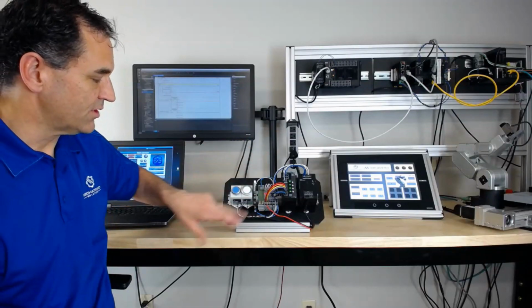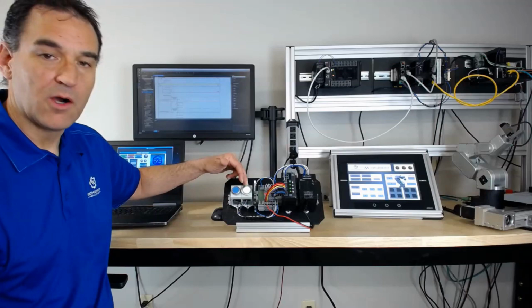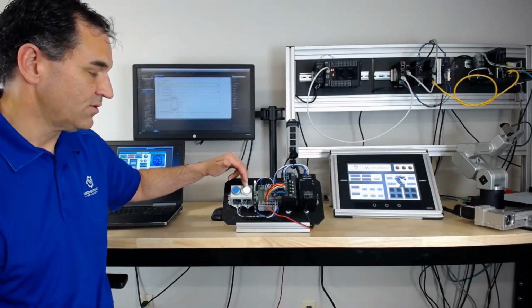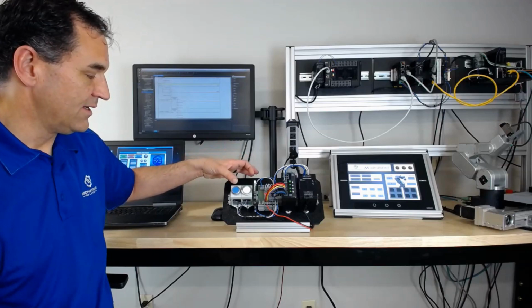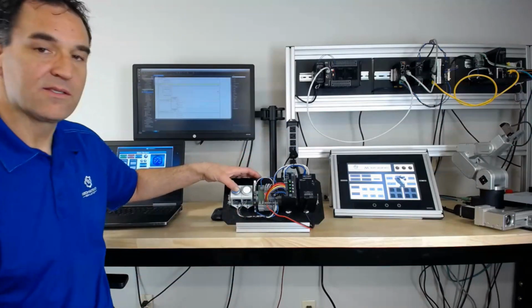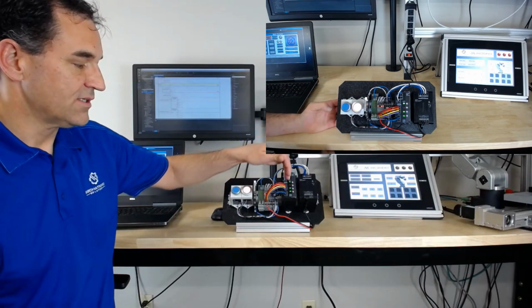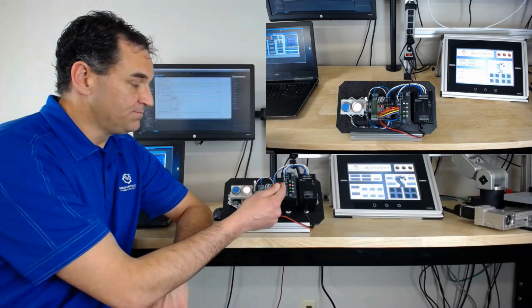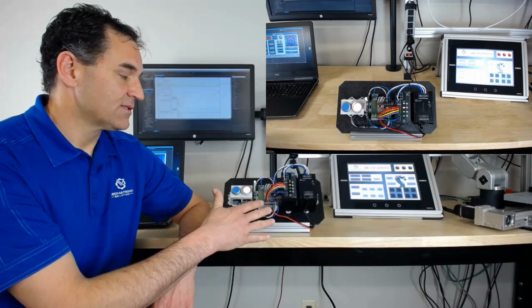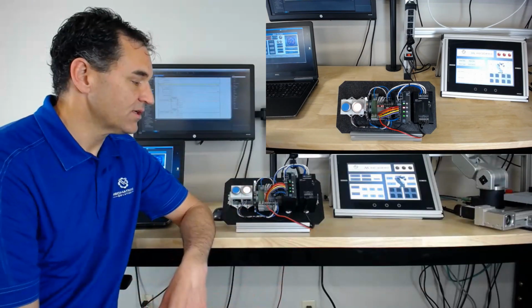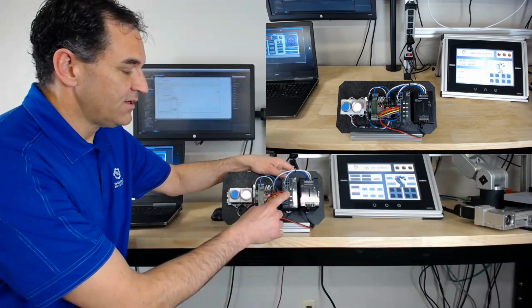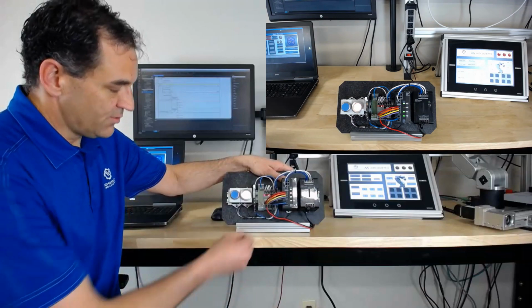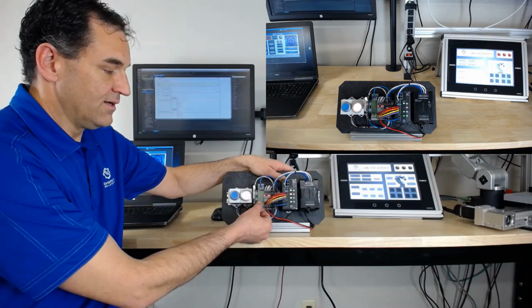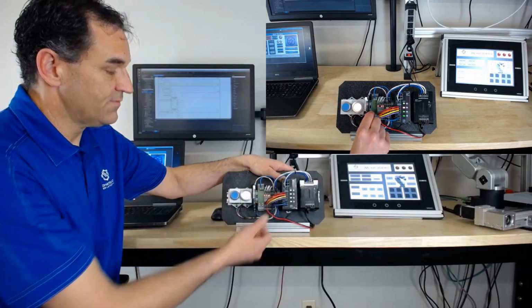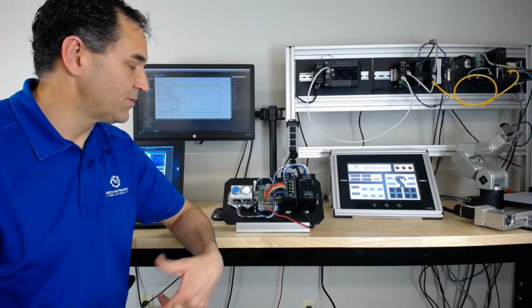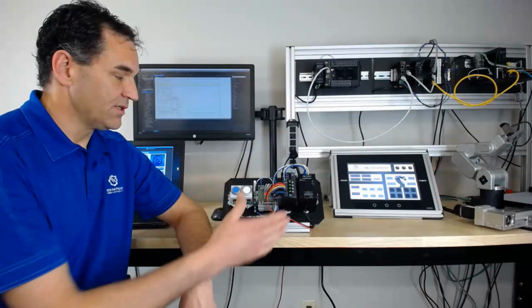I have a load tied to circuit 2, and I've got the alarm output tied to this indicator light. So you'll see this go red if we have a trip. And then I've got a remote reset. So I'm going to put a load on circuit 2. You'll see that starts flashing and has a 20-second delay. So it has to wait 20 seconds before you can reset the circuit. And so that red flashing light will turn to amber in the 20 seconds. And then I can do a reset right here. So that, be it from a PLC or an HMI, would then reset the circuit.